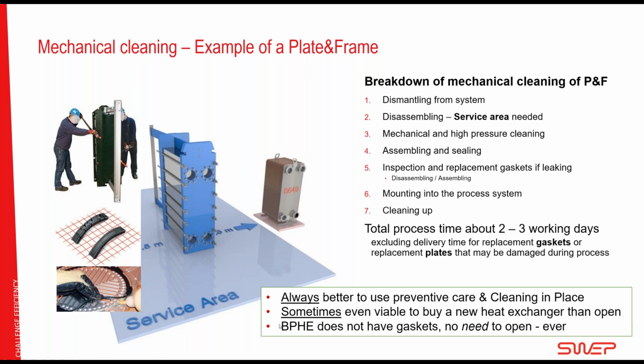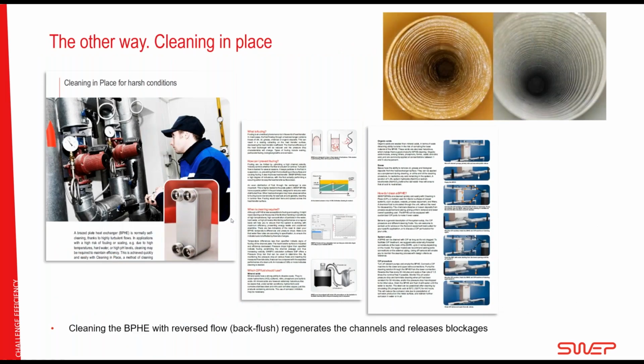I also know of situations where a plate and frame heat exchanger that needed to be opened and reconditioned, it was more economically viable to buy a new heat exchanger because it was too expensive to work on it. And since the brazed heat exchanger does not have gaskets at all, you will not find yourself in this situation. So what's the other option? Well, that's cleaning in place.